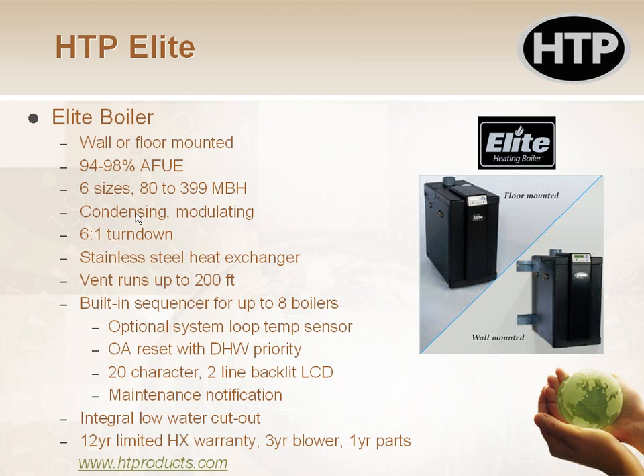So outside air reset controls not only get you a rebate from the gas utilities, they also save you quite a bit of money in the operation of that system. That's standard with these boilers. They have outside air reset controls built in, and they ship with an outside air reset sensor. They also have built-in standard controls to sequence up to 8 boilers. So if I wanted to put in, say, two 399,000 BTU sizes on a light commercial building and get a total of 800,000 BTUs, I can do that with two of these. Run a cable between them and add no additional control hardware.